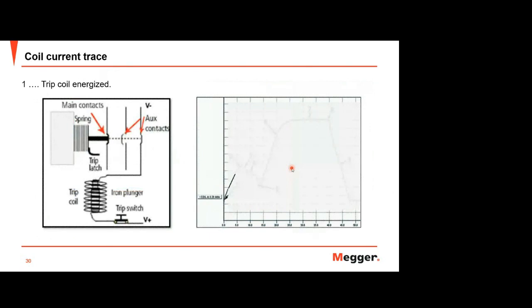Yeah, this is the illustration: the circuit breaker, coil, latching, and spring that can be used as the mechanical part to move the breaker from close to open or open to close. So this is the trip coil. In the middle is the plunger or armature, and this one is the trip latch. Trip latch means a part that can be used to hold the mechanical part of the breaker.